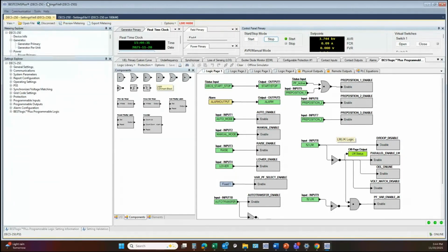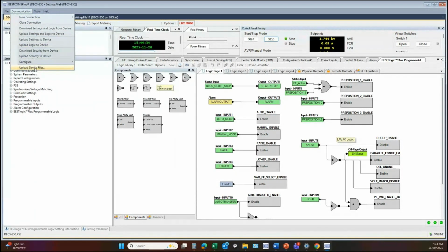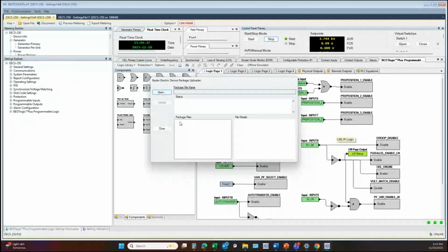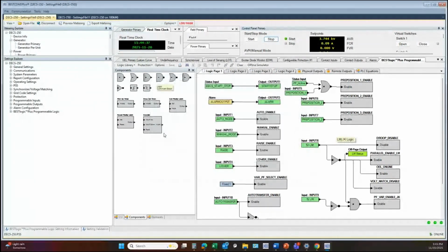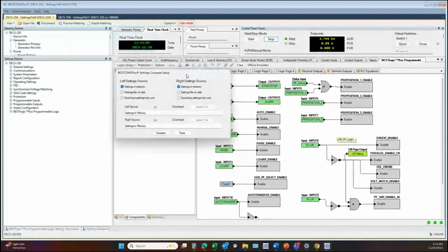If you're updating firmware, you would go up to communication and then upload device files. It would allow you to locate that firmware package file and then load that into the DECS. Furthermore, with the software, you can actually compare settings files.